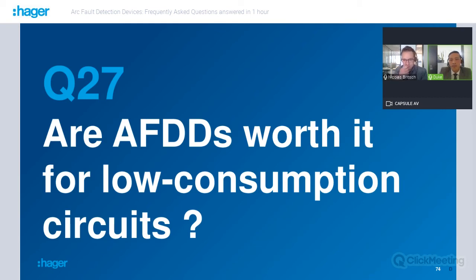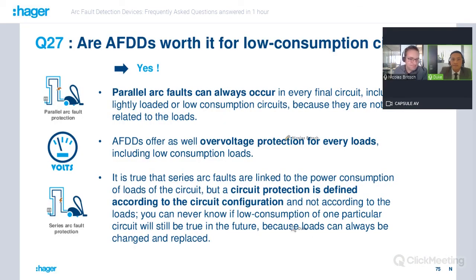So question number 27. Are AFDDs worth it for low consumption circuits? The answer is yes, because parallel arc faults can always occur in every final circuit, including lightly loaded or low consumption circuits, because they are not related to the loads. And AFDDs offer overvoltage protection for every load, as we already saw before, including low consumption loads. But I think this question comes when we talk about series arc faults.